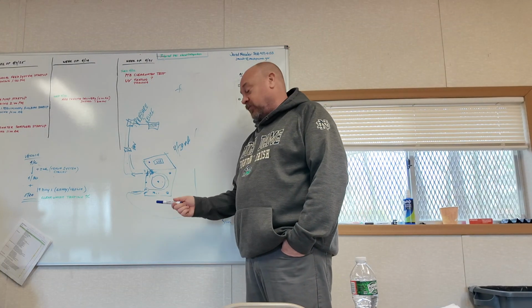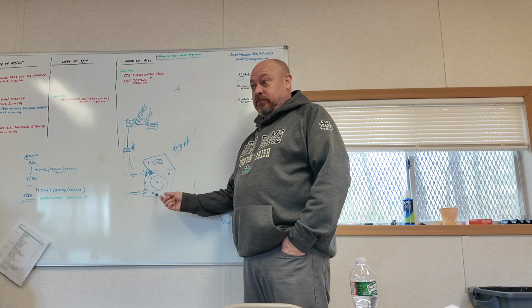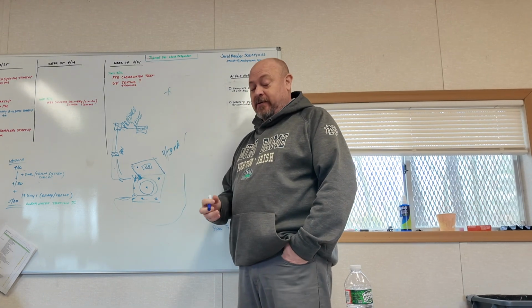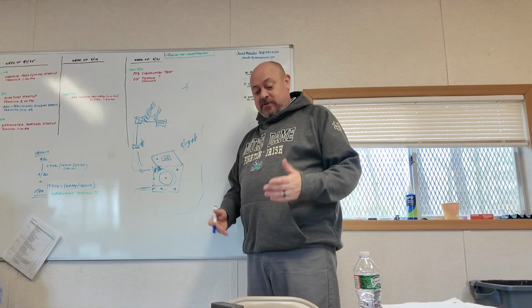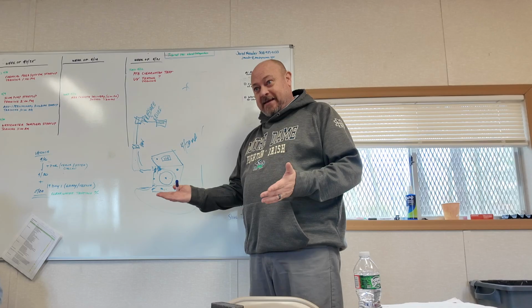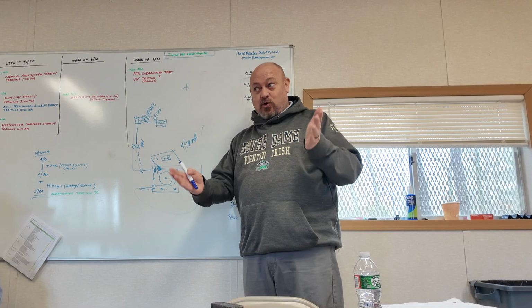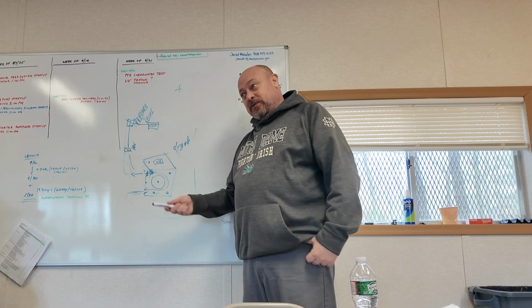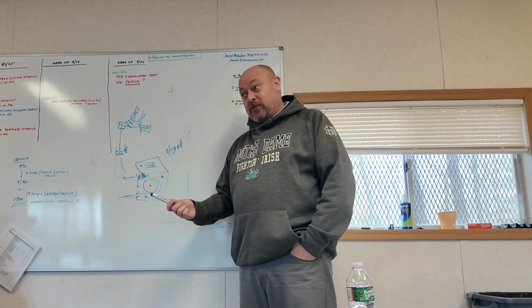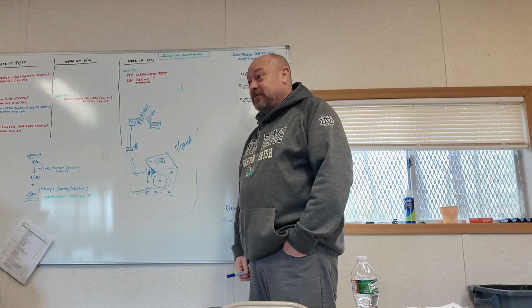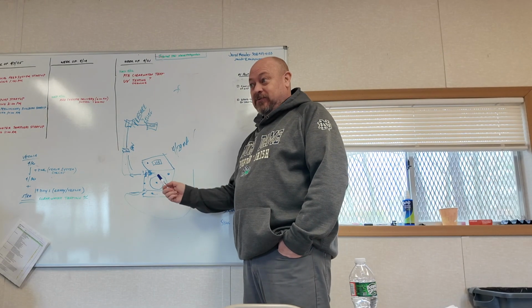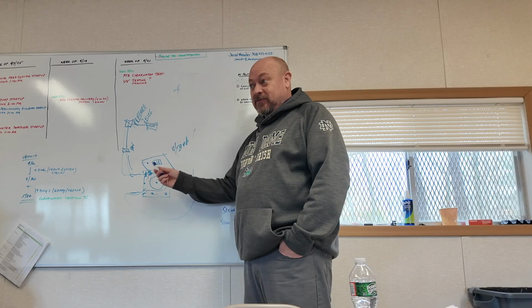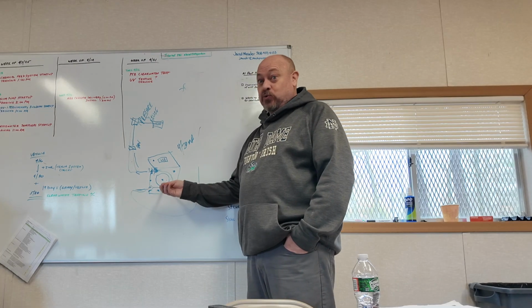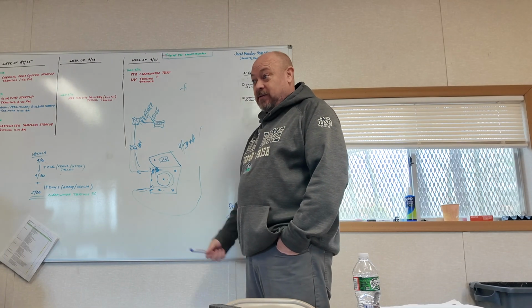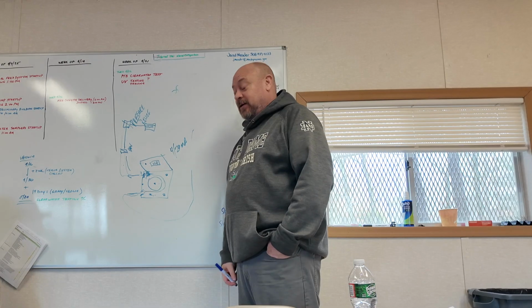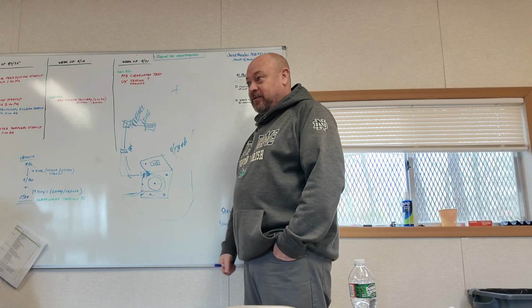Just one last note as far as maintenance on it. If you're not going to run the pumps, like say for example your citric acid skid, and I'm just going out on a limb here, right? One's going to be lead, one's lag, like standby, or you're going to alternate them one day. If you run citric acid through the pump and you're not going to run citric acid for another 6 months, do yourself a favor and flush this out, because I'll guarantee you if you leave citric acid in there, it's going to find a way to leak. And then when you go to use the pump, it's not going to run. And then you're going to call me up and say, hey, this thing sucks and I can't get it to pump. And I'm going to come down and this tube's going to be solidified to the point where this roller can't squeeze anything.